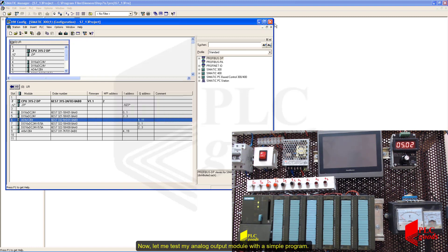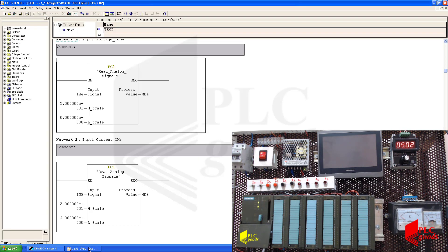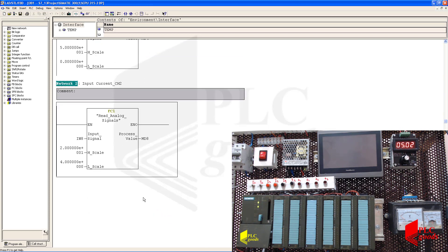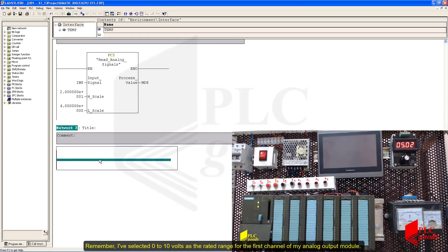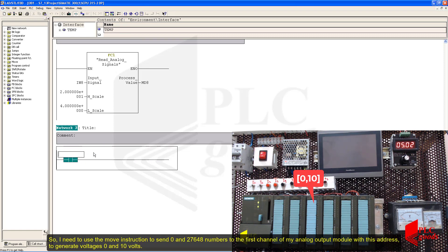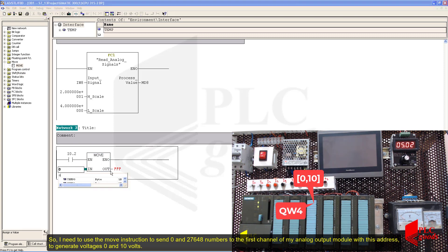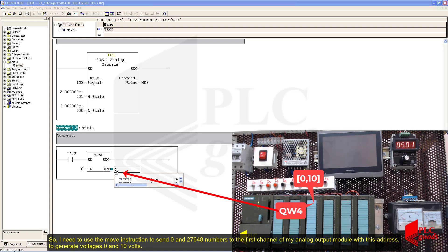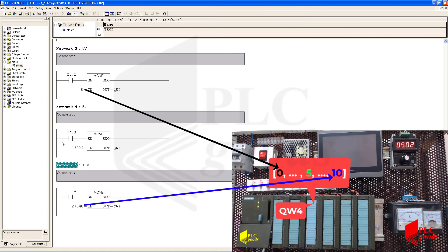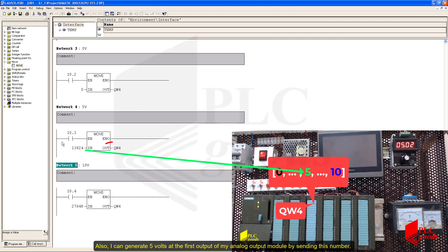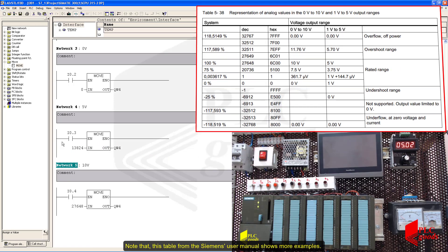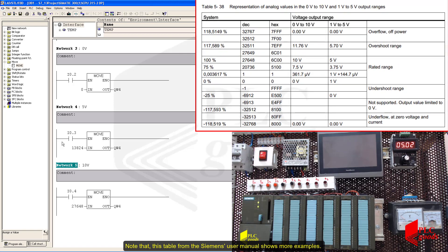Now let me test my analog output module with a simple program. I selected 0 to 10 volts as the rated range for the first channel of my analog output module. So I need to use the instruction to send 0 and 27648 to the first channel of my analog output module with this address to generate voltages of 0 and 10 volts. Also, I can generate 5 volts by sending the corresponding number. Note that this table from the Siemens user manual shows more examples.